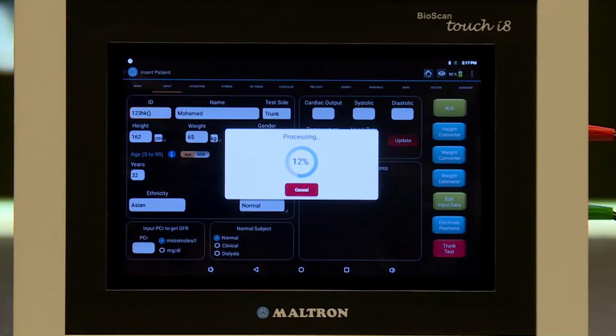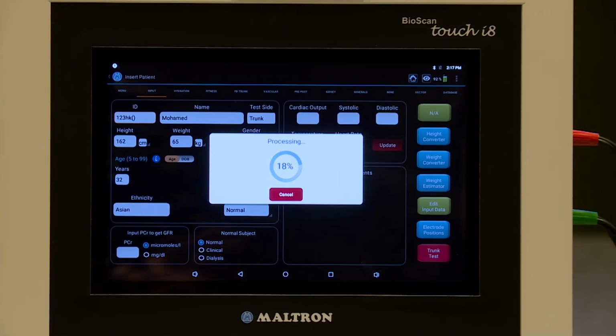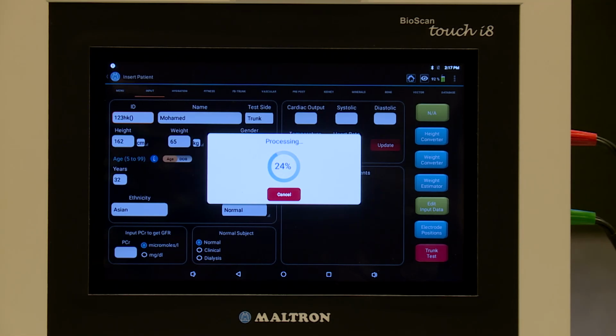So now it's processing. This is the measurements from right side, left side, crossing, and taking an overall average. On average, this takes 1 minute, 1 minute and a half? Yeah, about 45 seconds. Okay. What the machine does is it checks the electrodes, the cables, to make sure everything is connected. If there is a problem with the connection, then it will pre-warn you so that you don't make any errors in the data collection. By the way, the machine can store up to 1 million, 2 million patient data.